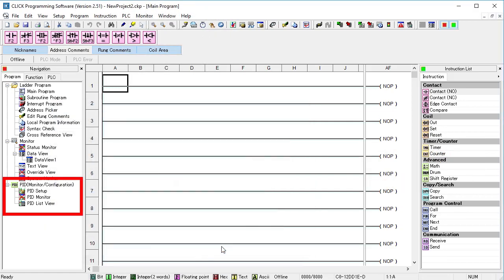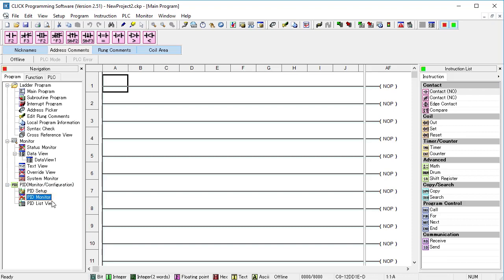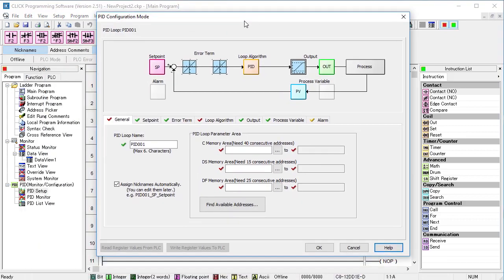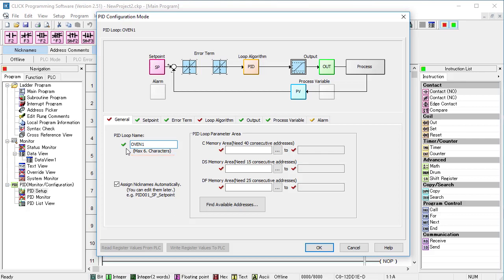The PID stuff is right here. For each loop, we can set up PID, monitor PID and get a list of all memory locations being used by PID. We want to set up a PID loop, so we double click on that one and give it a name. You are limited to 6 characters here because the loop name becomes part of the tag name. The 6 character limit keeps the tag name from getting too long.